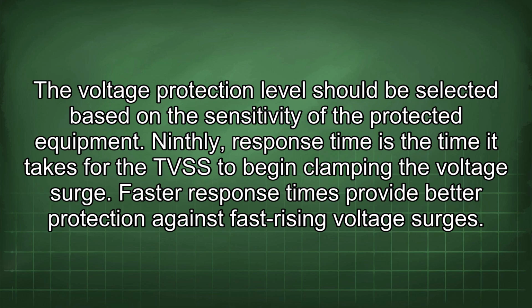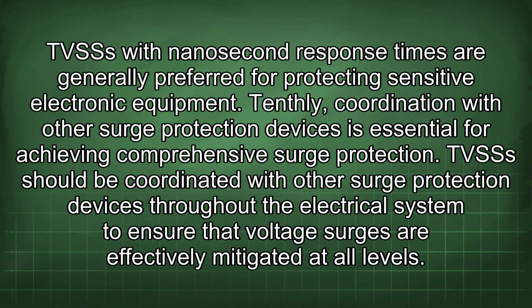Ninthly, response time is the time it takes for the TVSS to begin clamping the voltage surge. Faster response times provide better protection against fast rising voltage surges. TVSSs with nanosecond response times are generally preferred for protecting sensitive electronic equipment.